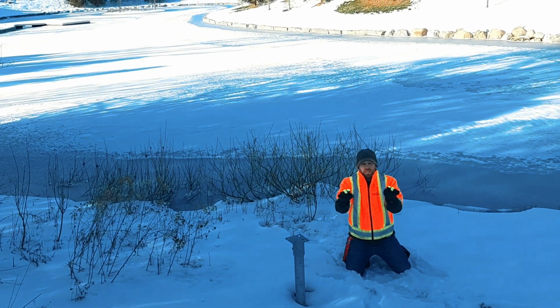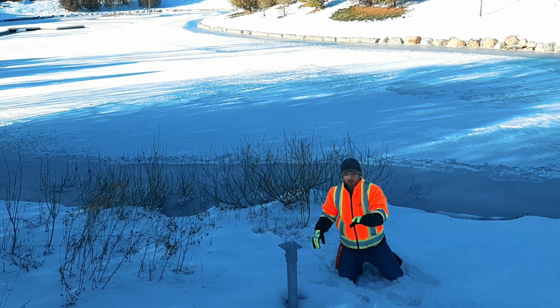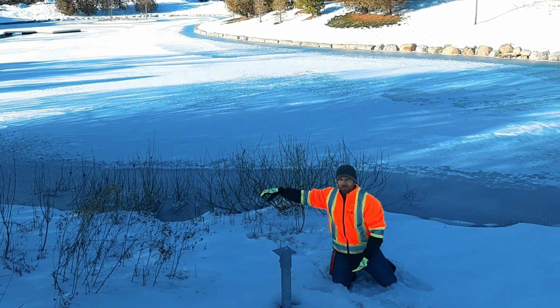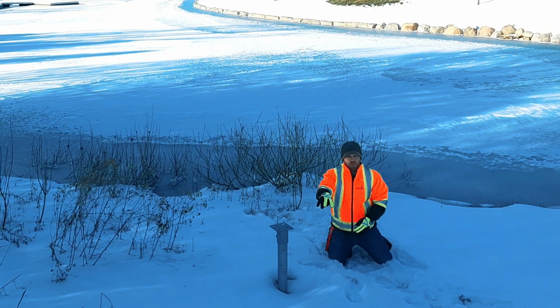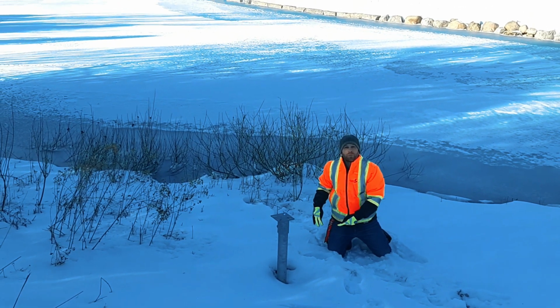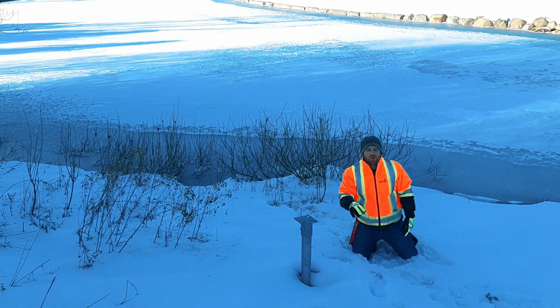Yep. In the winter time, let's say November each year, turn the pumps off, close the gate valves, undo this union, get rid of that piece, put another one in that doesn't have a check valve. Gotcha. So now if the pump goes off, the water can go back out. Throughout the summer you don't want it to, because then you have to recharge that whole pipe and it's hard on the pumps, right?